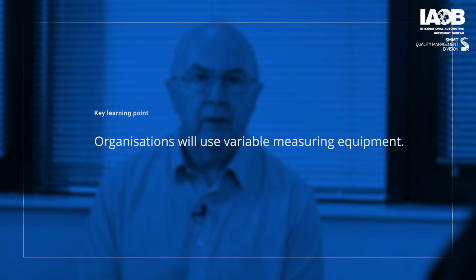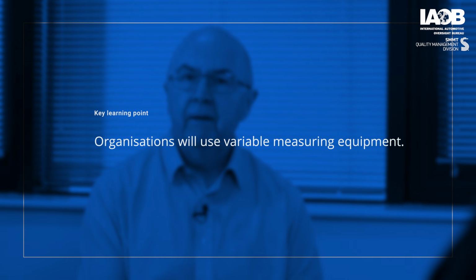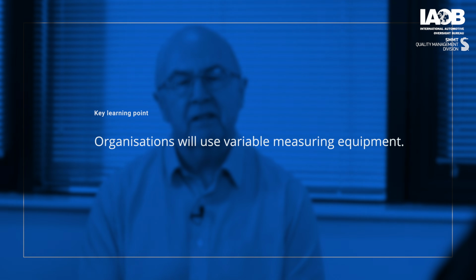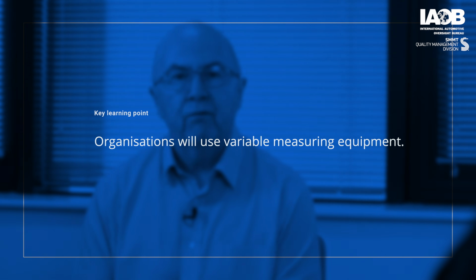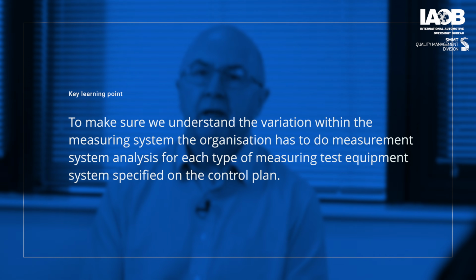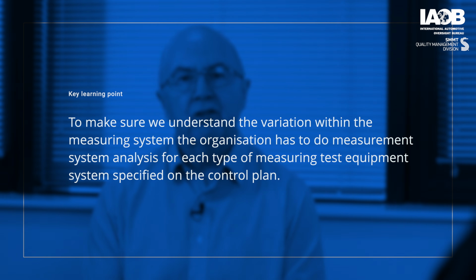Let's summarize then. Organizations will use variable measuring equipment. Devin's given some examples: it could be micrometers, hardness testers, tensile testers, where we're actually getting a variable measurement value from the measurement system. To make sure that we understand the variation within the measurement system, the organization has to do measurement system analysis for each type of measuring test equipment system specified on the control plan.